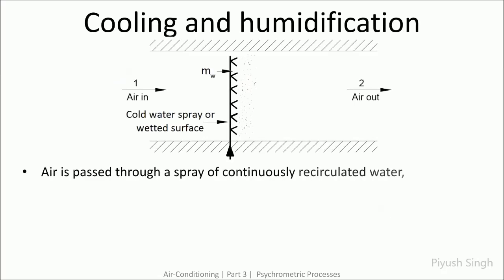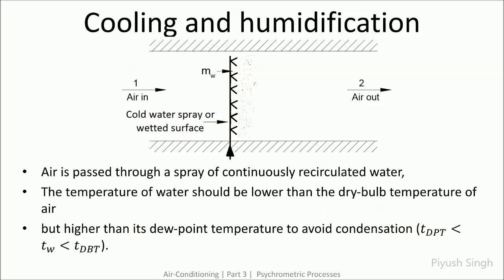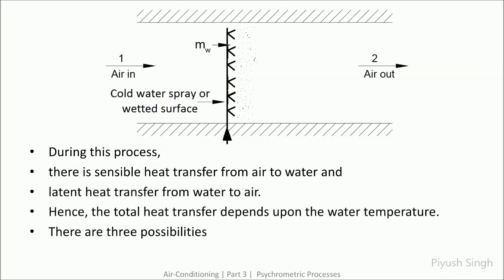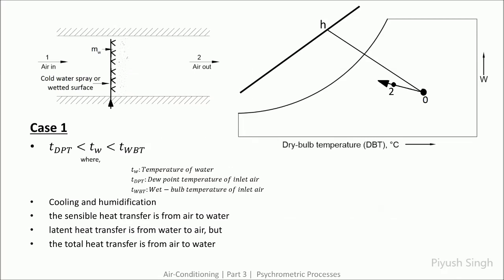The next process is cooling and humidification. A spray of water is added to the incoming air; the water temperature should be lower than the dry bulb temperature but higher than the dew point temperature. During this process, there is sensible heat transfer from air to water and latent heat transfer from water to air, so the total heat transfer depends upon the water temperature. There are three possibilities: if the water temperature lies between the dew point temperature and the wet bulb temperature, cooling and humidification takes place and the total heat transfer is from air to water, resulting in a drop in enthalpy of the air.